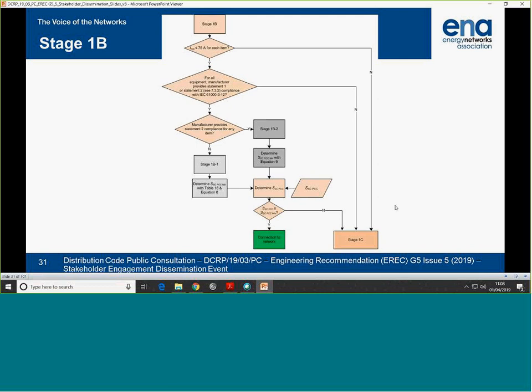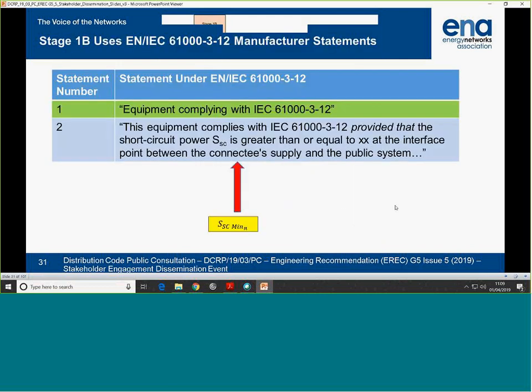Based on high-powered domestic products and some industrial will fall in the scope of this document. There are 15 amps and up to 75 amps in that range. More EV chargers can fall into this range as well. So in this flow chart, you have a limit which is basically saying, is the equipment less than 75 amps? Does it qualify to be treated under this standard? Then the process splits into two parts, stage 1B1, stage 1B2. In simple terms, stage 1 covers equipment where they can simply say, this equipment complies with 61312. Stage 2 is a more complicated case where at least one item is subject to a required fault level being met. The exact statements that they have to make are on the next slide.